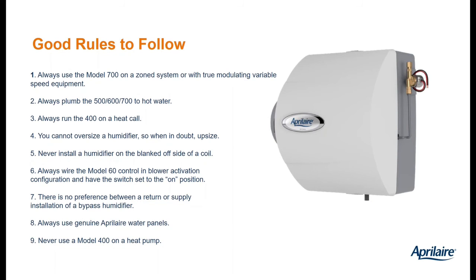Here are some general good rules to follow, and I'm going to give you a little bit of context for each one, because I think that some of these are a little bit overstated, let's say. So the first one: always use the Model 700, which is our power humidifier, so no bypass, if you have a zone system or a true modulating variable speed system, where it's ramping up and ramping down, so you could have very, very low airflow sometimes. The power humidifier, the Model 700, is very forgiving to changes in airflow, and that's inherent to a true variable speed HVAC system, and to a zone system with motorized dampers in the ductwork.